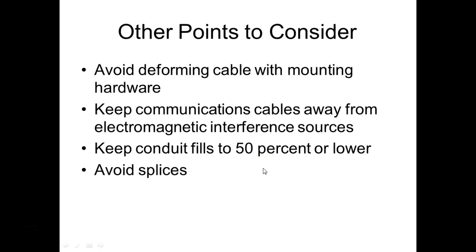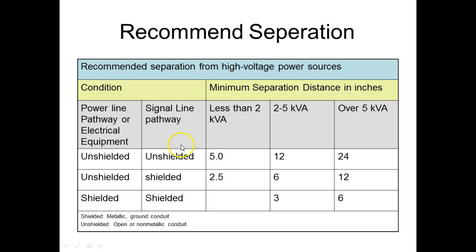Of course, we need to avoid deforming the cable when mounting hardware. Keep communication cable away from electromagnetic interference. And we've got another chart that's coming up. Keep the conduit fill to 50% or lower, and then avoid splices. So this is your recommended separation between these power lines. So unshielded, these are all shielded.